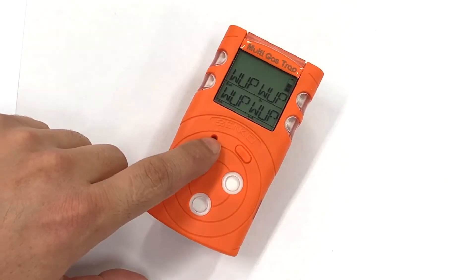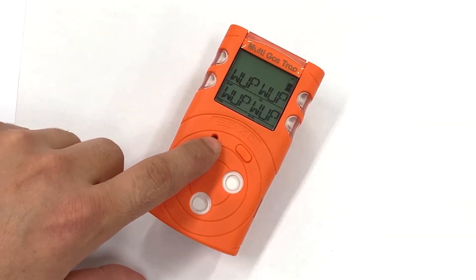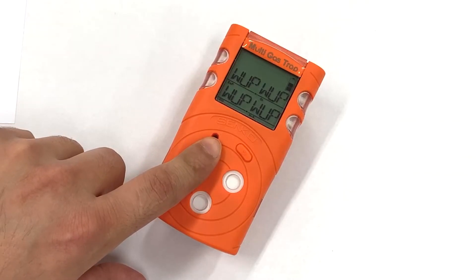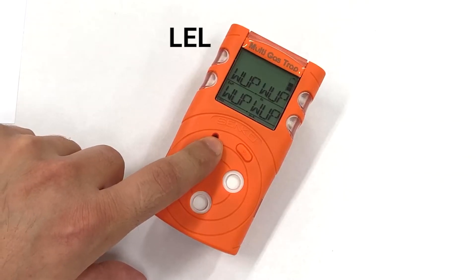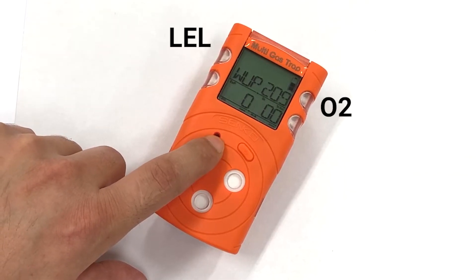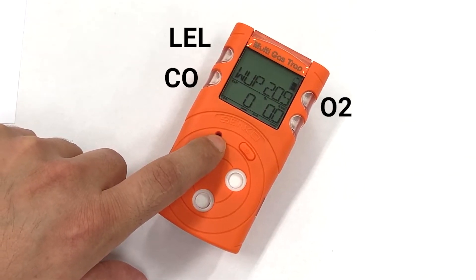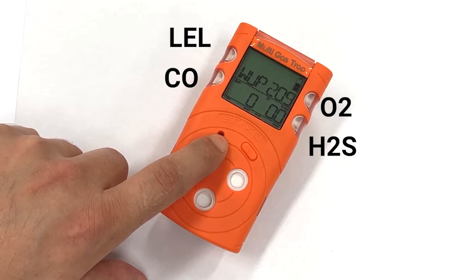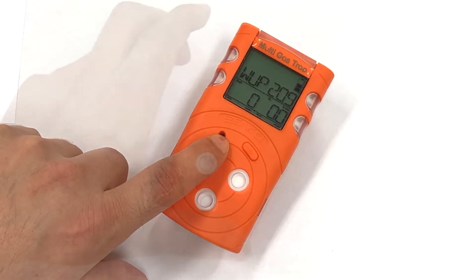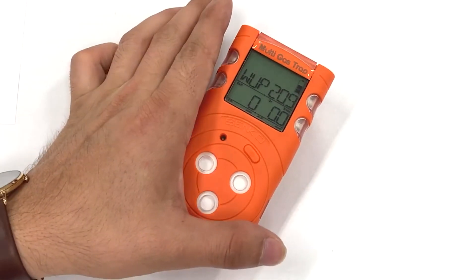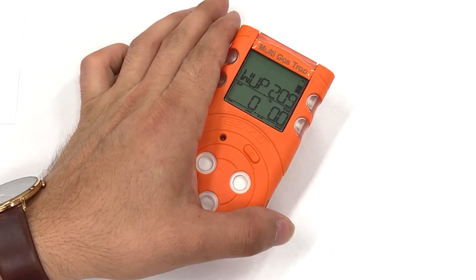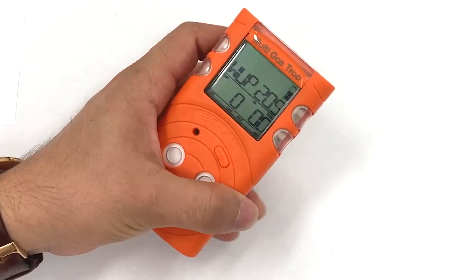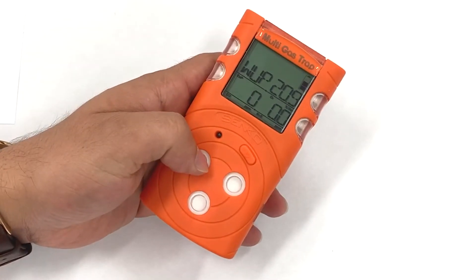As we can see, we have full gas measuring with combustible gases, oxygen, carbon monoxide, and hydrogen sulfide instantaneously. Warning and danger alarms, as well as STEL and TWA alarms, are available.